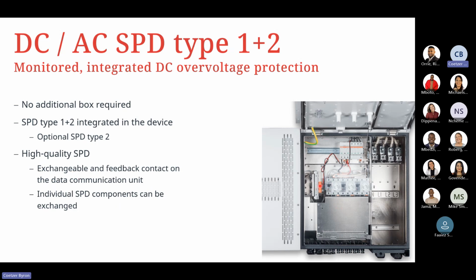So the unit will physically communicate with the pilot device. If either the DC or AC side has failed, we can simply see with the data that's output to SolarWeb, and we'd be able to tell what exactly has failed before going out to site.